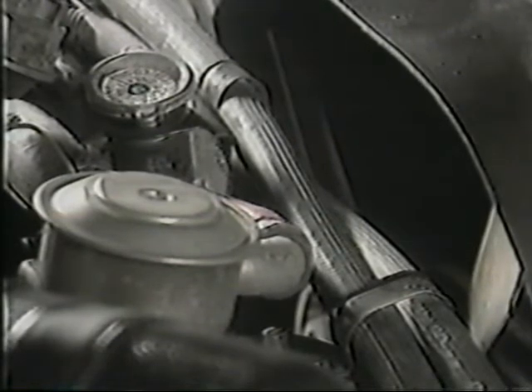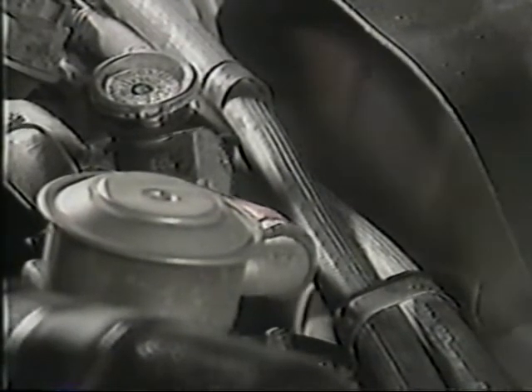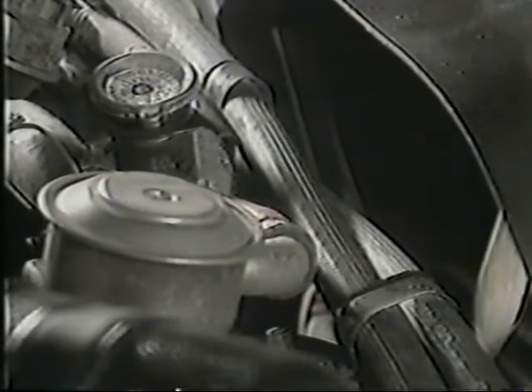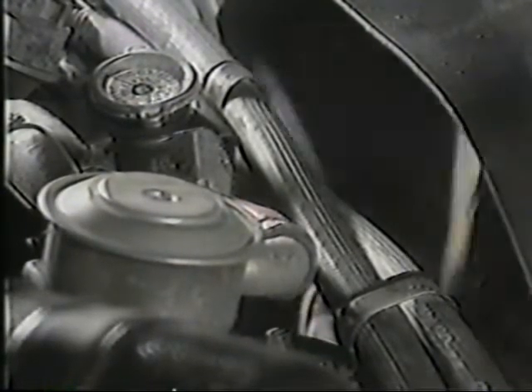If the engine is not started immediately, the override switch will stay closed for 30 seconds and then it will turn off. At this point, the override may be turned on again by engaging the starter. This brings voltage up on the start or brown wire terminal, which activates the override for another 30 seconds, turning the fuel on and permitting the engine to be started. Our final point about the 9038, 9041, 9042 series also concerns the override. For high temperature or low coolant shutdowns, the override operates as many times as the starter is engaged, giving 30 seconds of engine runtime for each engagement. But after a low oil pressure shutdown, engaging the starter gives only one 30-second override period. After that is gone, the engine shuts down and cannot be restarted.